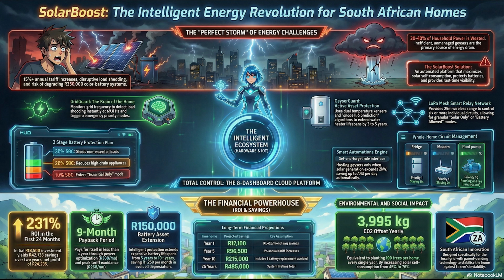Life is good. But let's say this isn't a quick 2-hour outage. A substation blew up and you are facing a 6-hour blackout. A very realistic scenario. The hours tick by. The battery slowly, steadily drains. It hits 50%. It hits 40%. The system is monitoring, but nothing changes yet. But then, the telemetry data reports the battery has hit that first threshold, 30% SOC. The RTOS immediately triggers stage 1 of the load shedding plan.